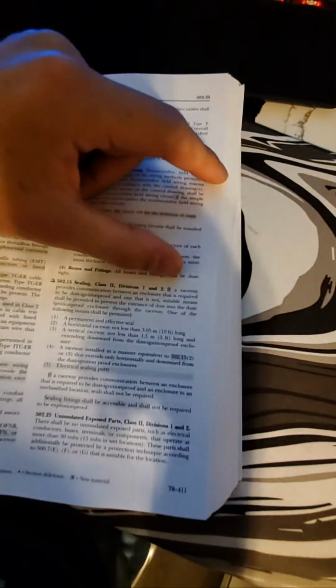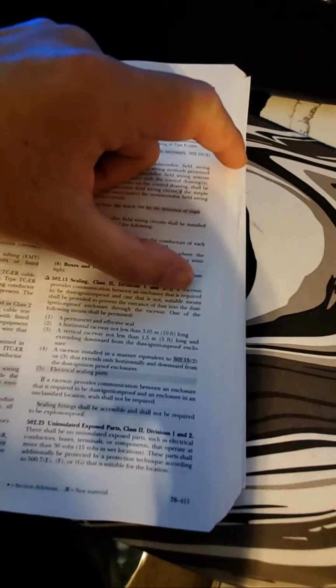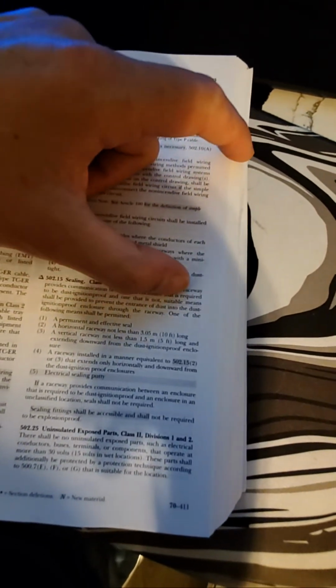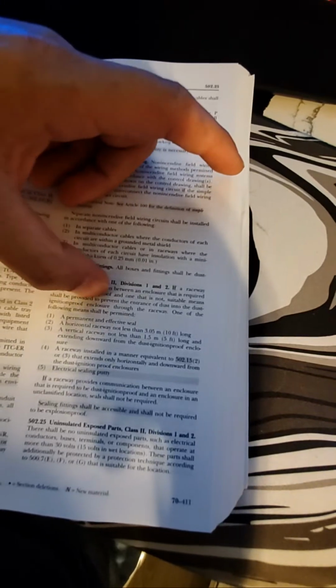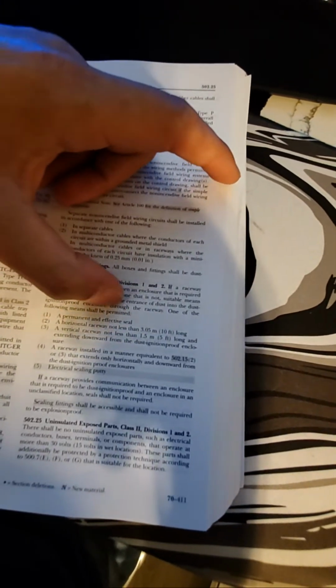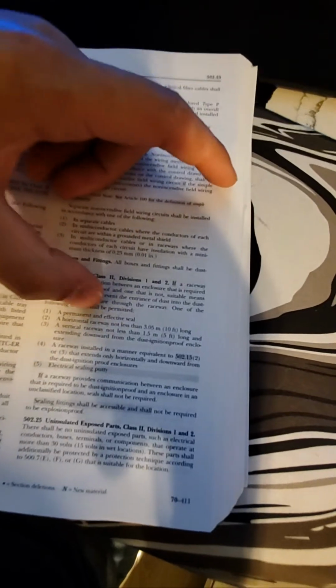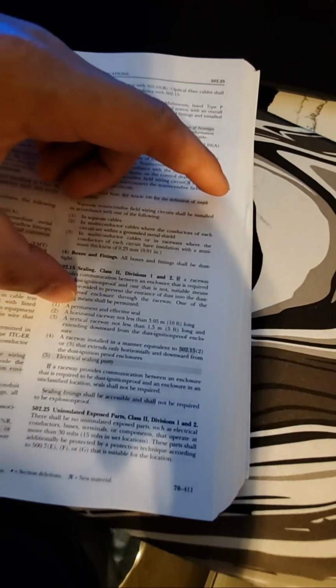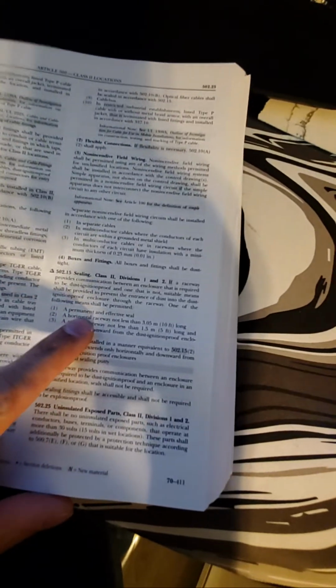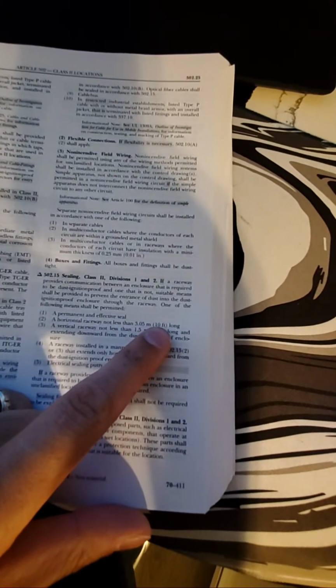Let's try to read it again. If a raceway provides communication between an enclosure that's required to be dustproof and one that is not, suitable means shall be provided to prevent the entrance of dust into the enclosure through the raceway. One of the following. So just one of the following. Check it out. The raceway is not less than 10 feet. So you need one. Either you need a seal or you can go more than 10 feet. That's your answer.